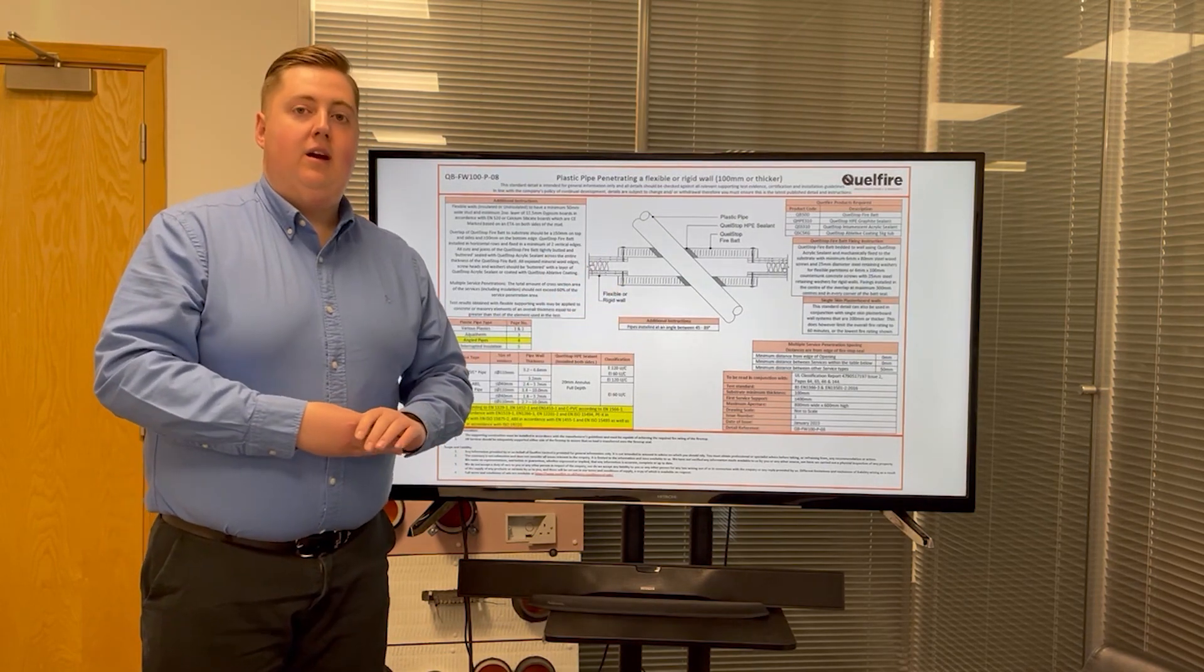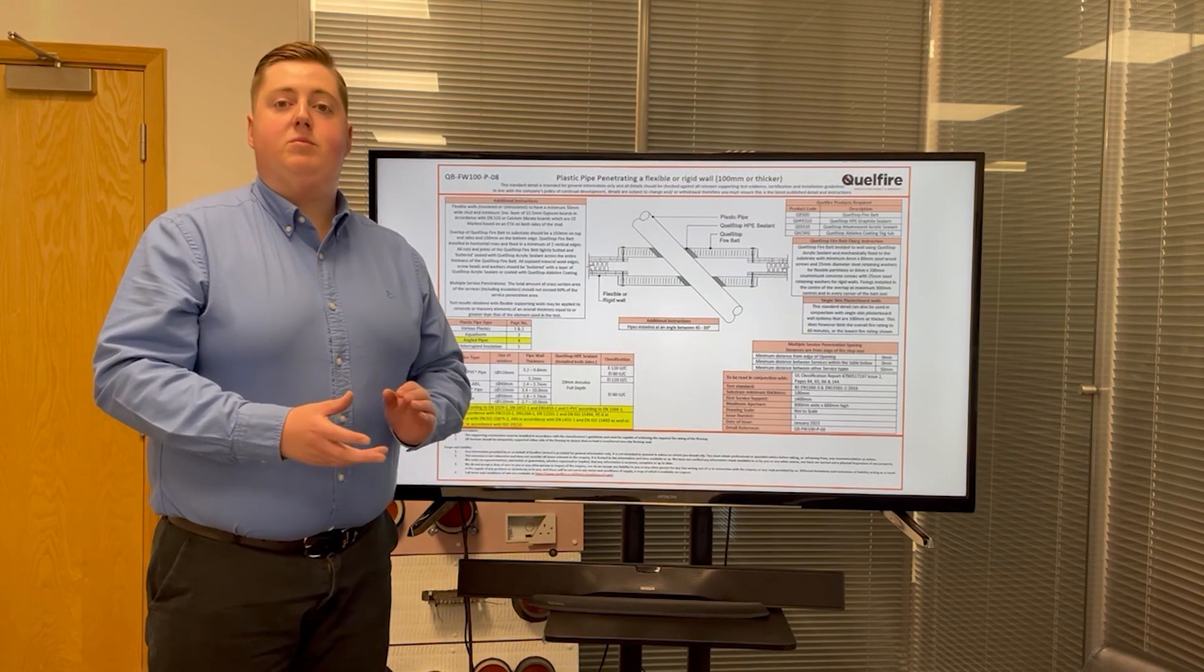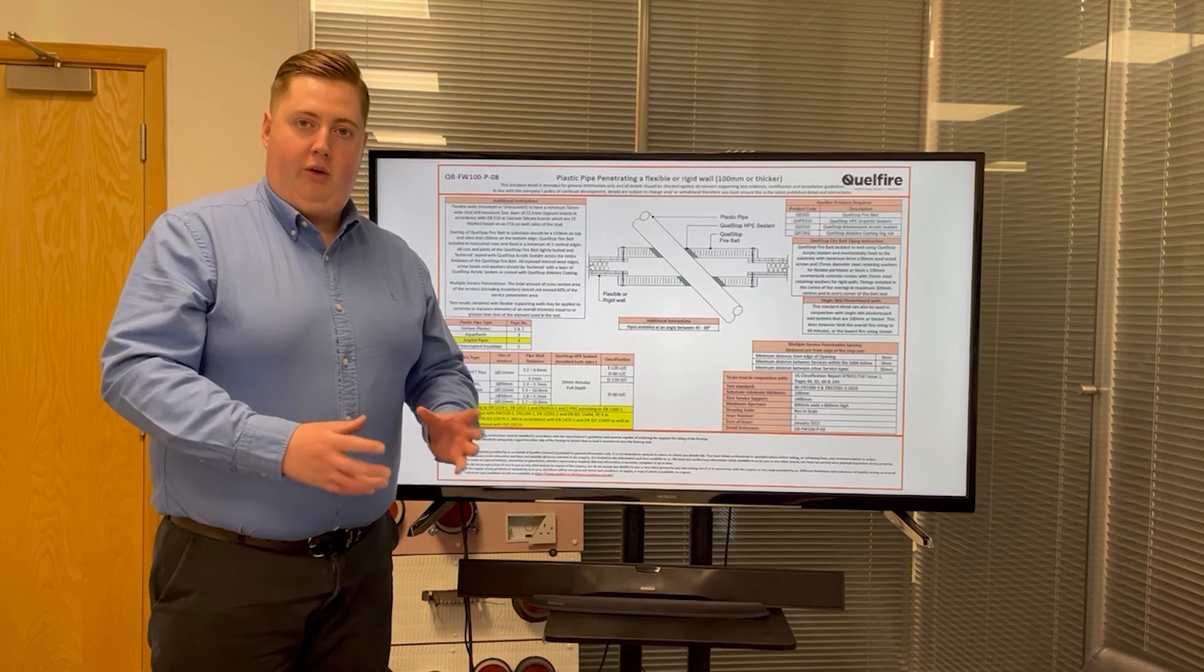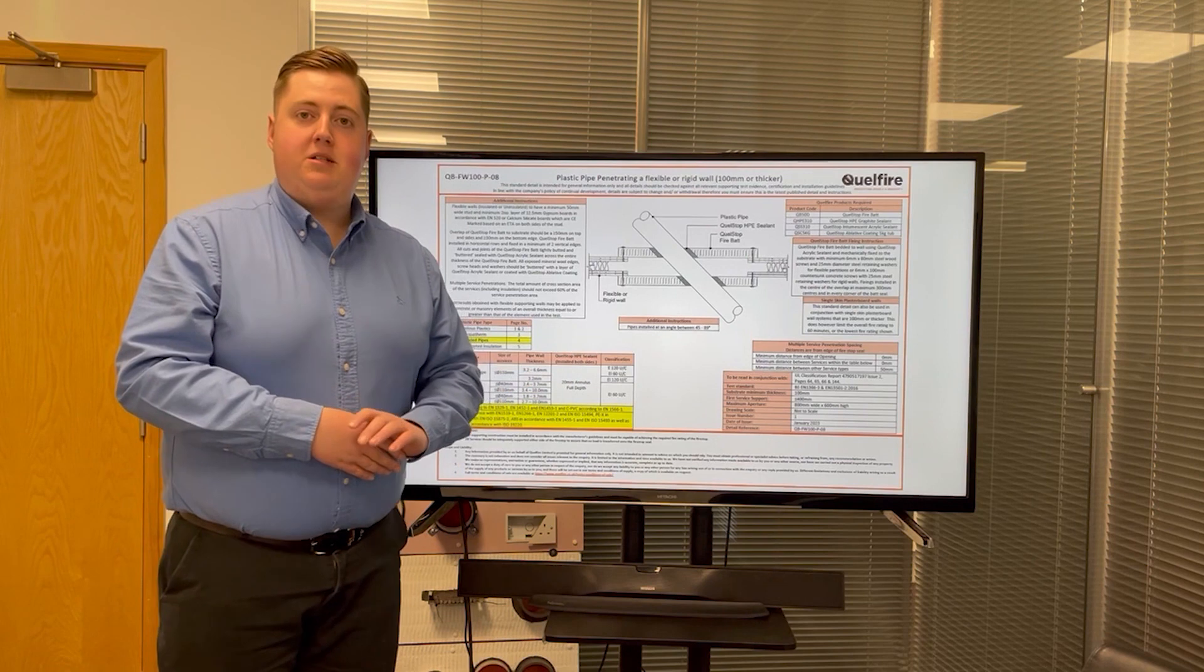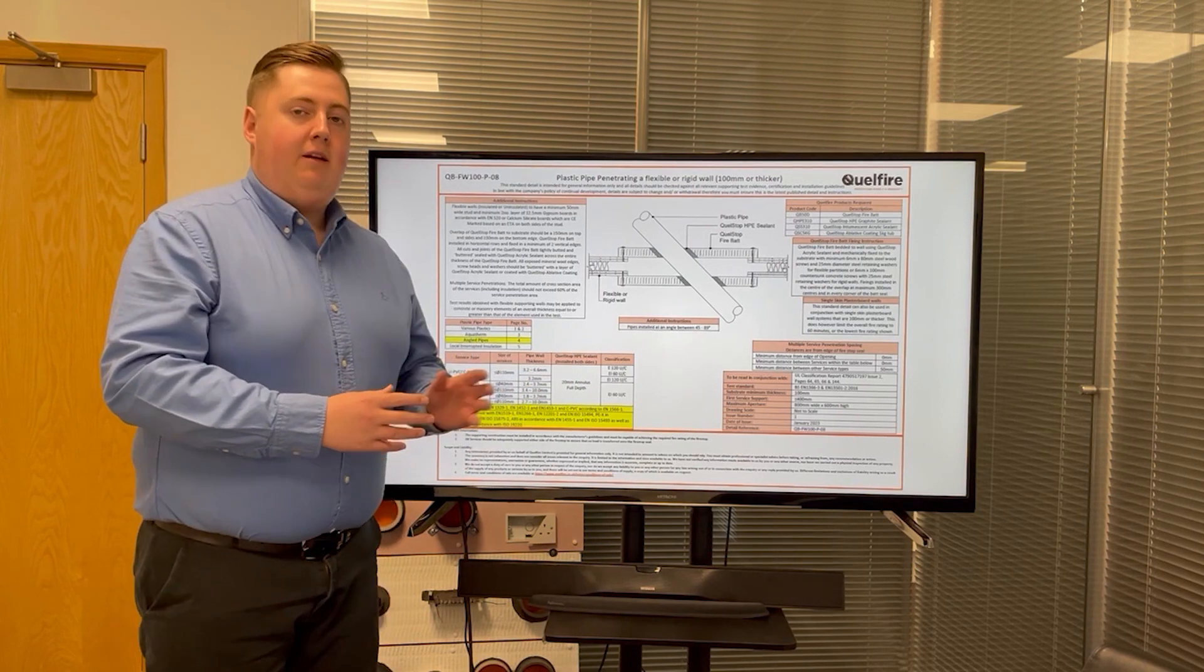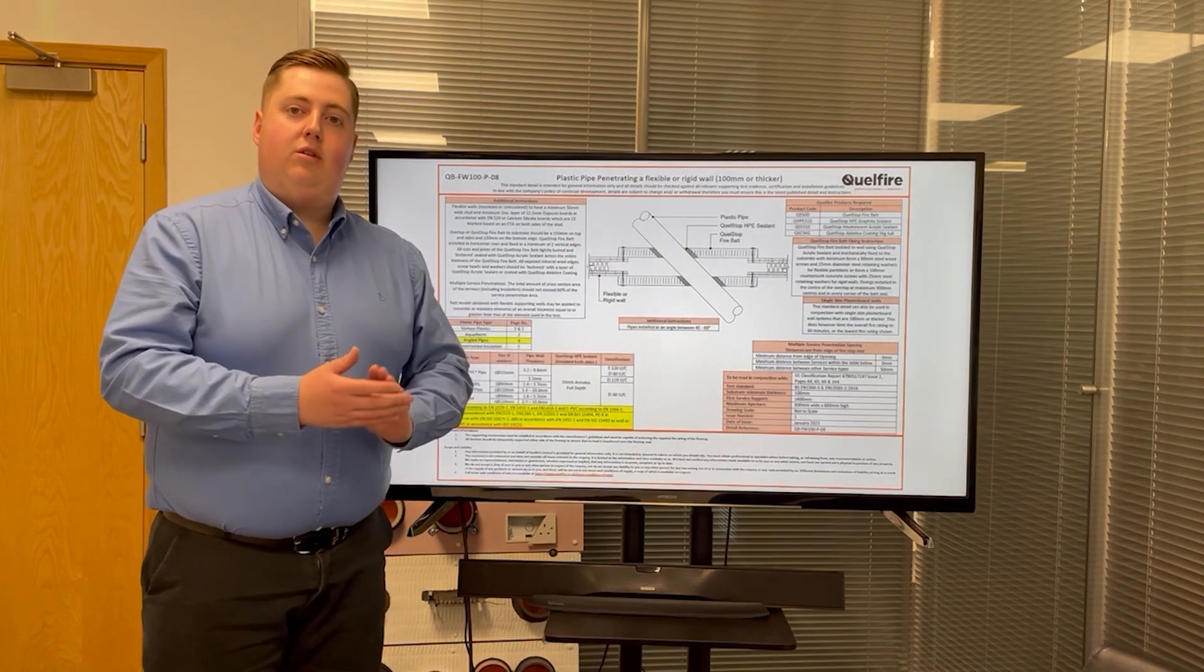We've also tested insulated copper pipes, insulated with non-combustible rock fibre insulation and sealed using the Quellstop intumescent acrylic sealant, again at angles between 45 degrees and 90 degrees through the wall.